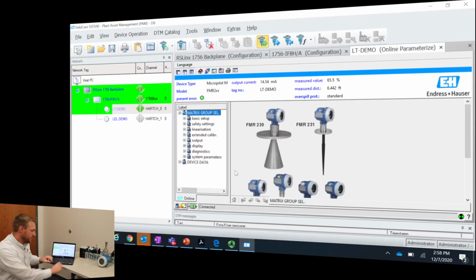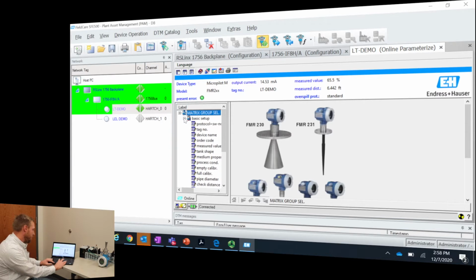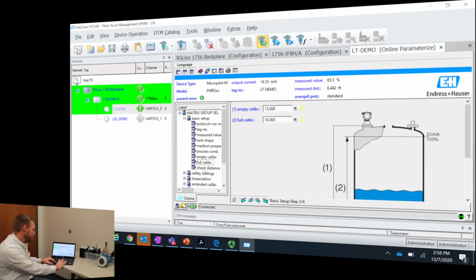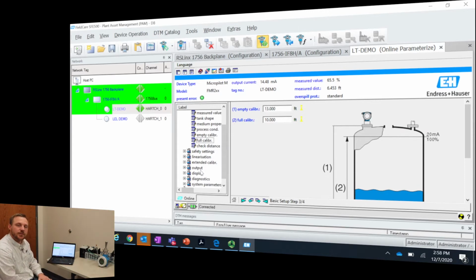If we wanted to change the basic setup of it and rescale it for the measuring range, we could go under basic setup. We could change things such as measured or tank shape, medium property, process condition, all fairly important conditions for setting up this device. And then finally we could also change the full and empty calibration, which essentially sets up the scaling of the device, when it puts out 4 milliamps, when it puts out 20 milliamps. There's a bunch of other options in here also for things we can change on this device to set it up for the process we're working on.